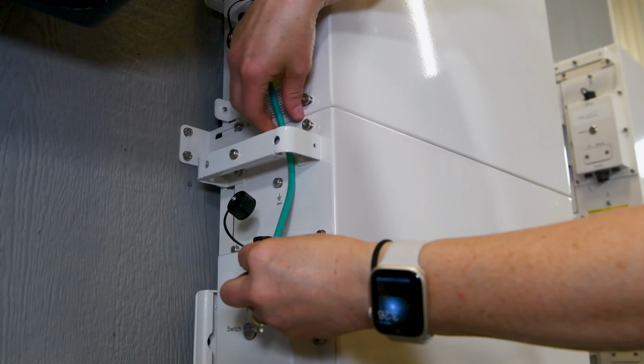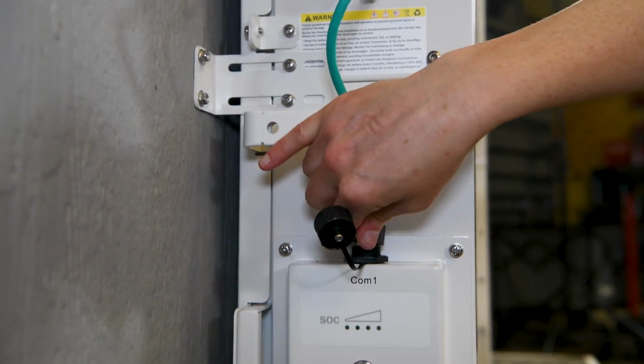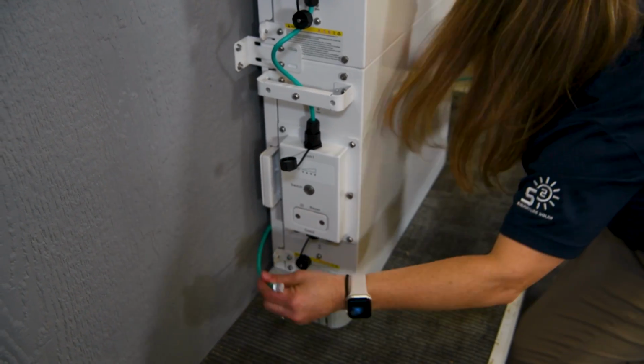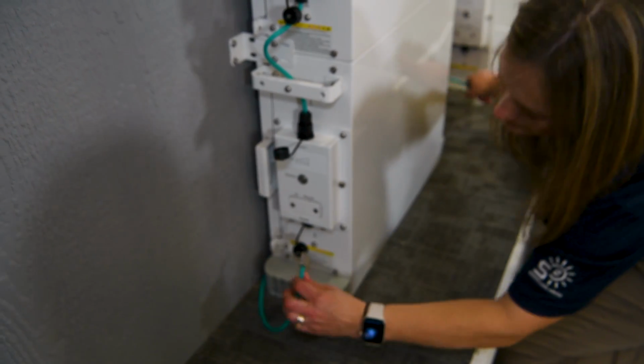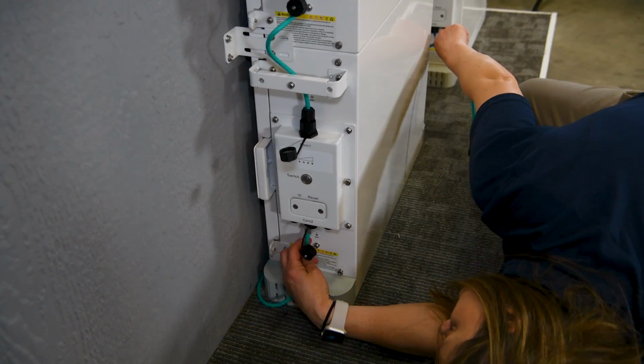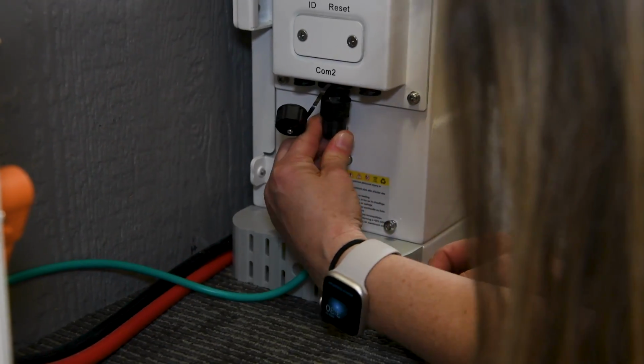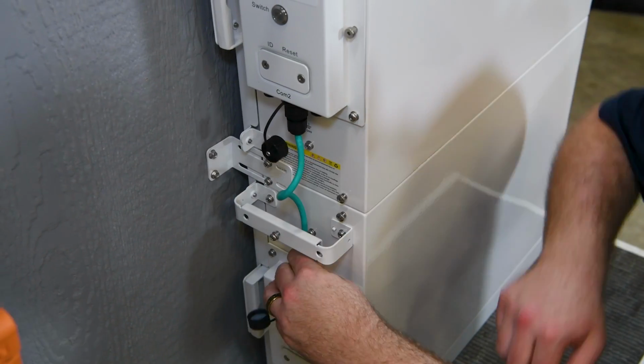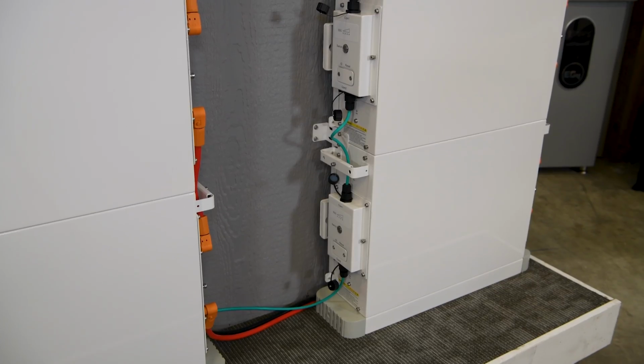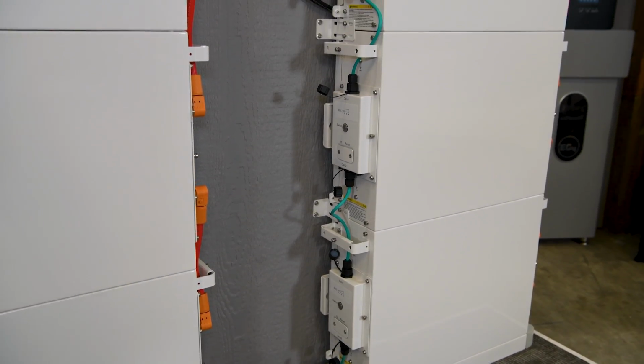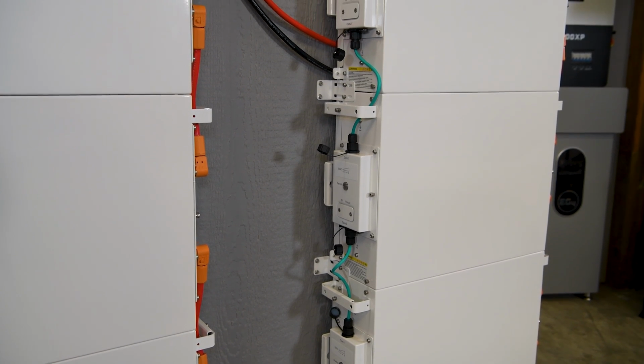in this manner. When reaching COM port 2 on the last battery module, we'll need the longer communications cable from our extra cables kit to connect to COM port 2 on our second battery stack. Continue daisy chaining them up to the top battery module of the second stack. This setup ensures all modules can communicate seamlessly in a closed loop system.